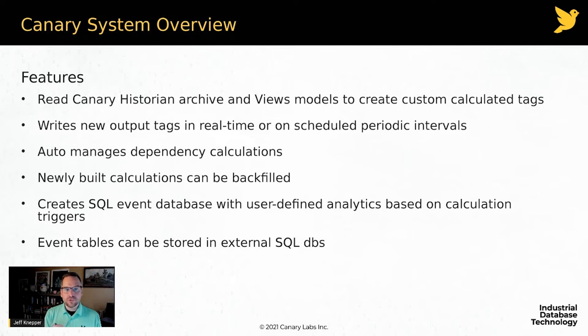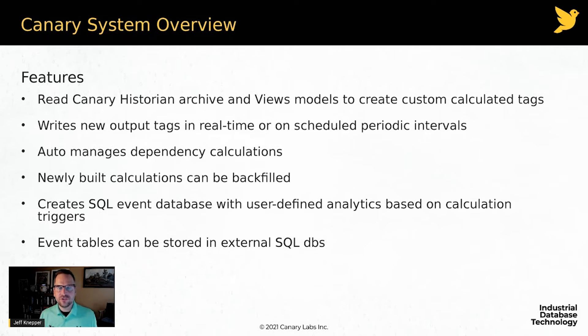The Calcs and Events server reads all data inside the historian through Views and through the models you build in Views, so you can create custom calculated tags and custom event tables. With a new calculated tag, you have two capabilities: you can output the tag in real time on change, or you can configure it to run a calculation every five minutes, every hour, every shift, every week, or every month — completely configurable inside the calc server.